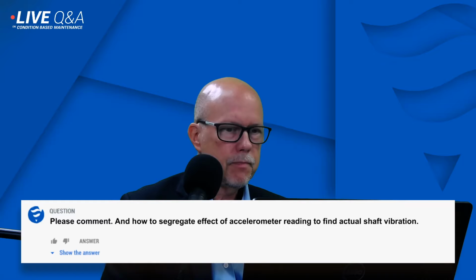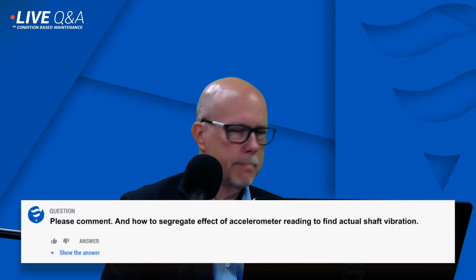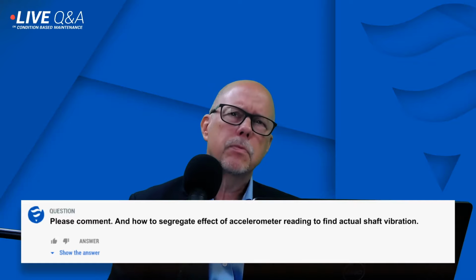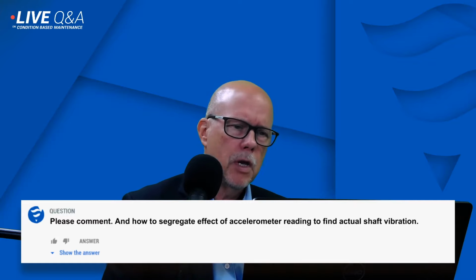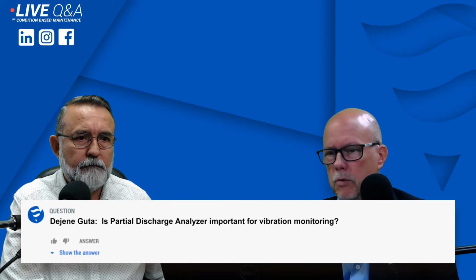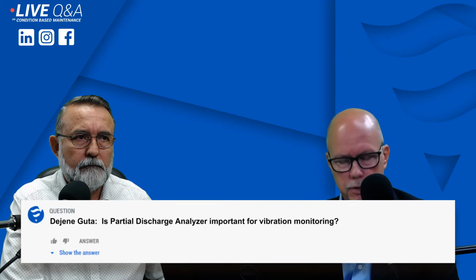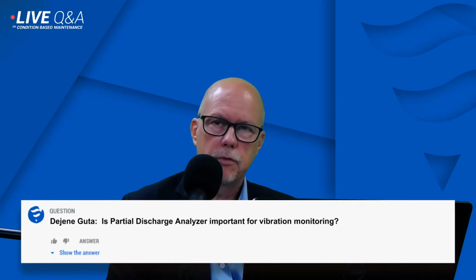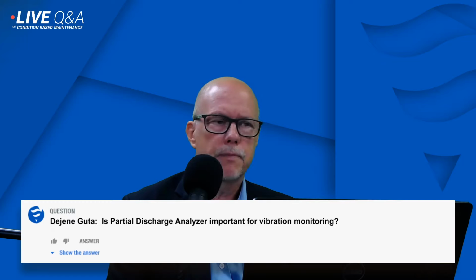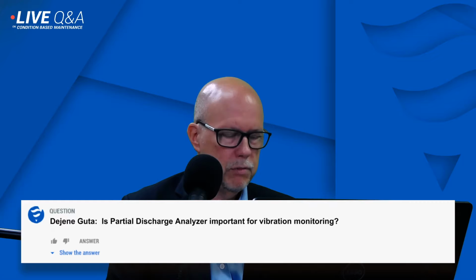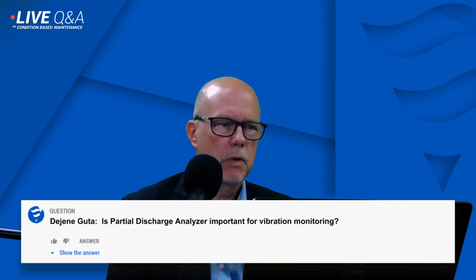We have another question from Dejan Gutta. I'm sorry if I'm not pronouncing it properly. Is partial discharge analyzer important for vibration monitoring? Well, I know that some partial discharge vendors will tell you that they're able to measure vibration based on slot discharge. Well, that's a little misleading from my view because, as I've mentioned before, our objective as a monitoring system provider is to detect and prevent damage, not to observe it. We don't want to record the damage, we want to record the behavior and prevent it.